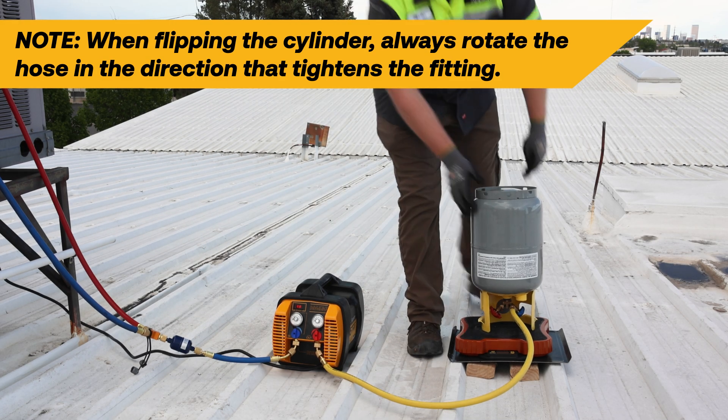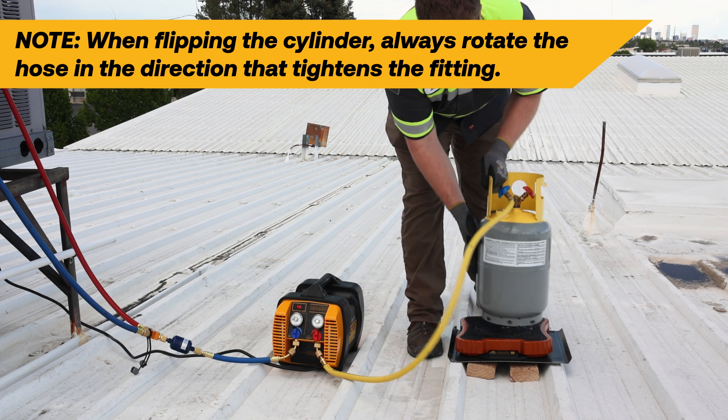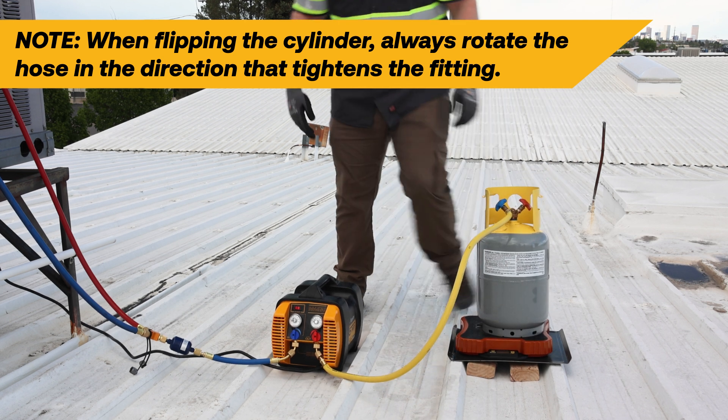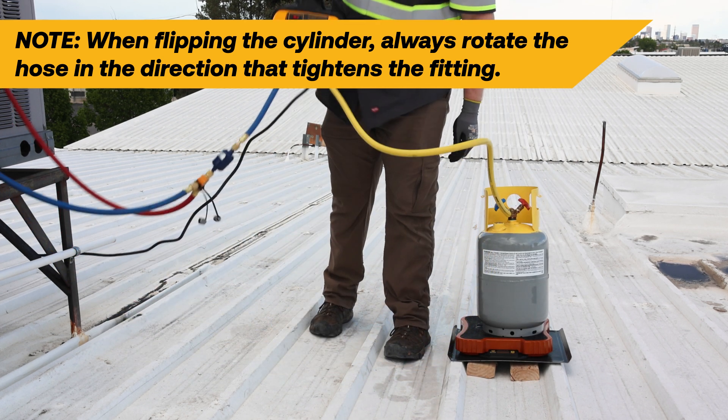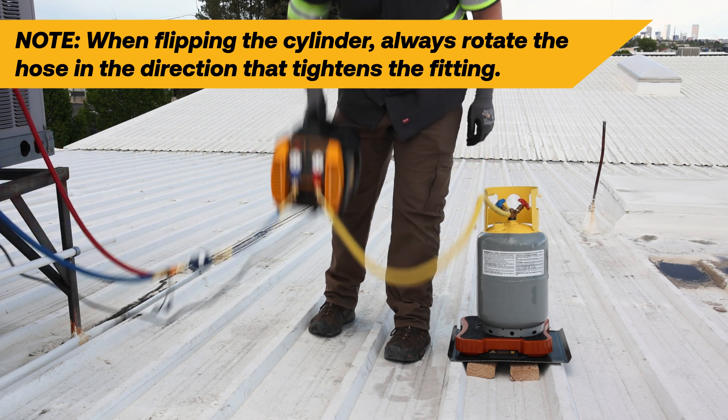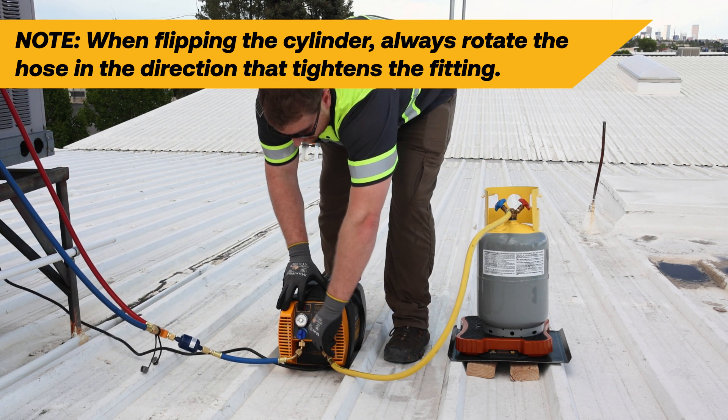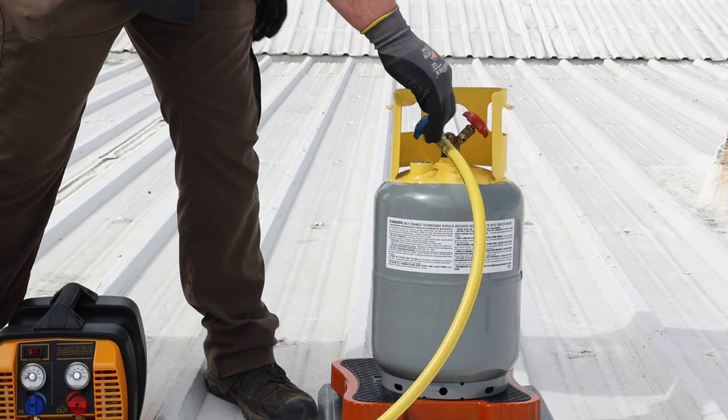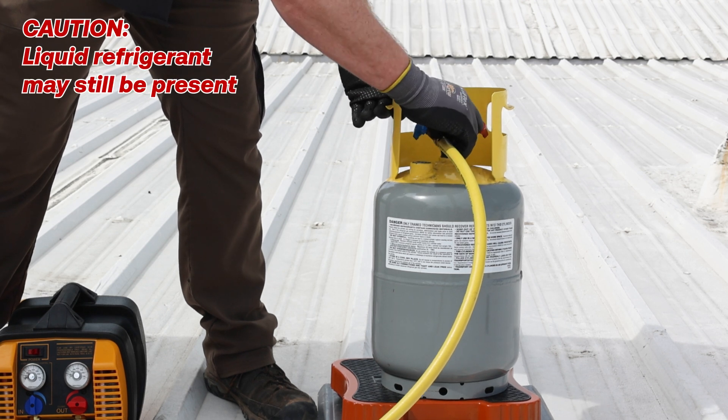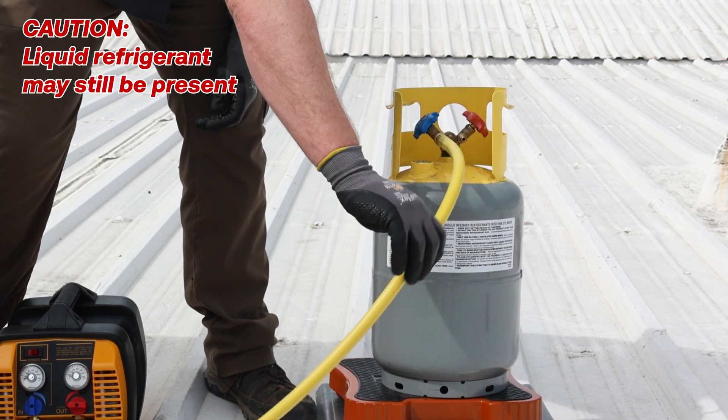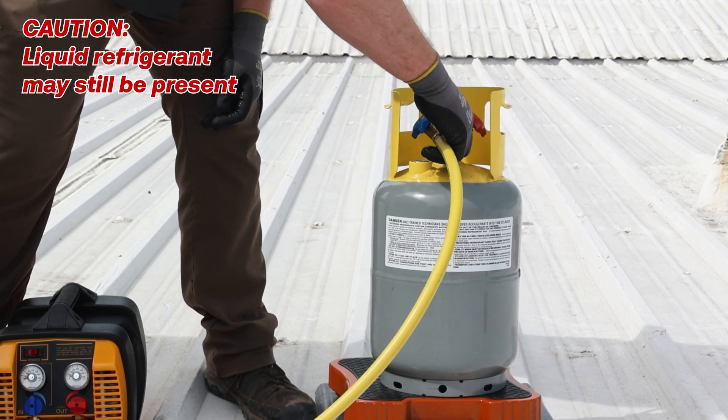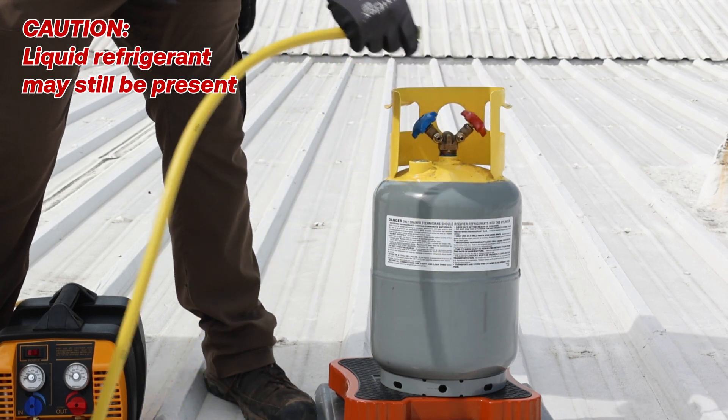When recovery is nearly finished or the recovery cylinder being used is ready to be swapped out for another cylinder due to capacity limitations, the cylinder can be flipped upright. With the cylinder upright, any remaining liquid refrigerant in the output hose can migrate to the recovery cylinder. Clearing the output hose of liquid refrigerant will reduce unnecessary refrigerant loss during the disconnection of the hose after recovery has been stopped.